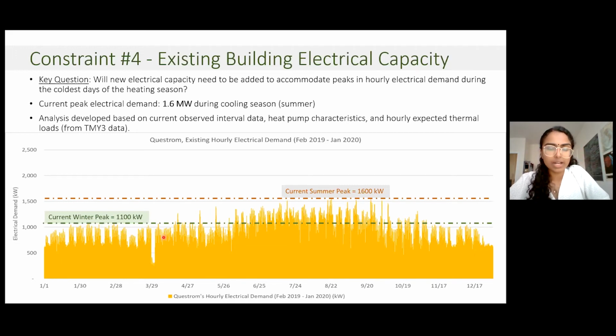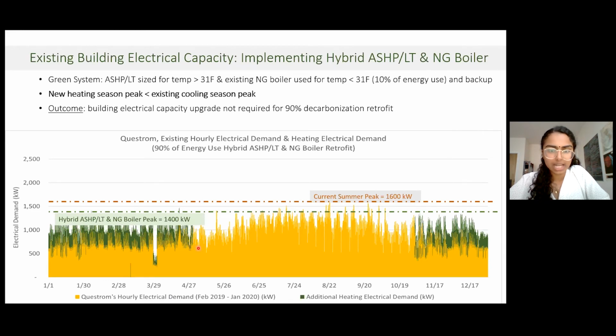And what we found is that even if our heating electrification solution will increase our existing heating electrical demand, as long as it does not exceed the cooling season peak, we can actually keep our existing electrical capacity. And so what we've done here is we've modeled implementing this hybrid low temperature air source heat pump and natural gas boiler system with our existing electrical capacity. And so what we found is that since we don't exceed this cooling season peak, we don't need to engage in an expensive and cumbersome electrical capacity upgrade in order to achieve that 90% decarbonization.